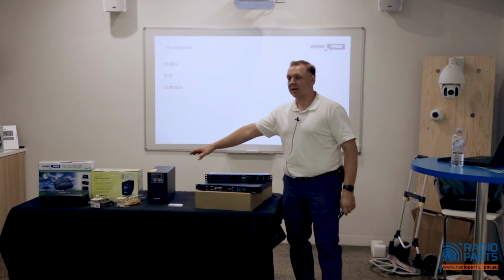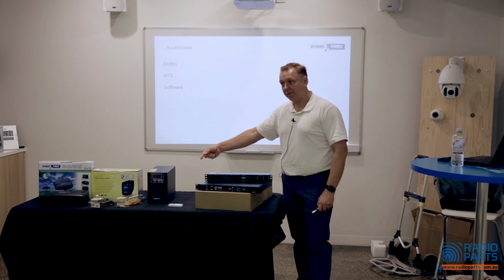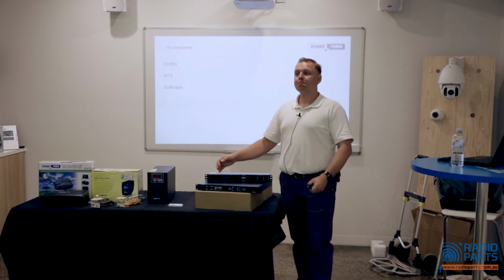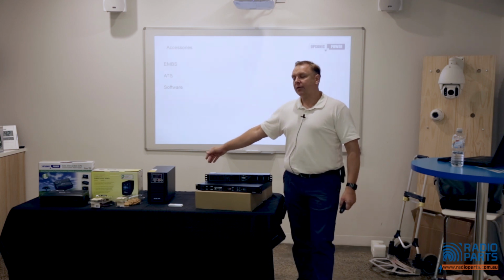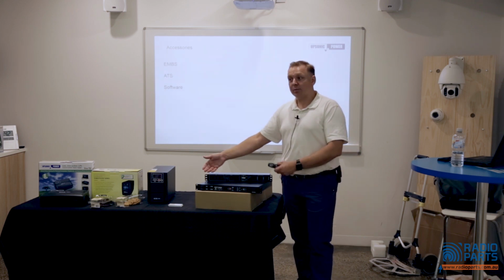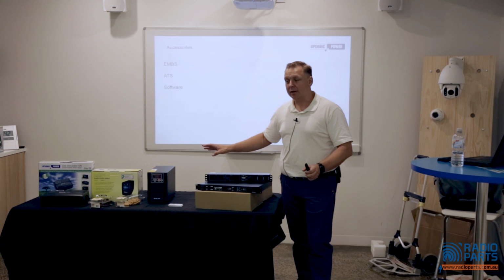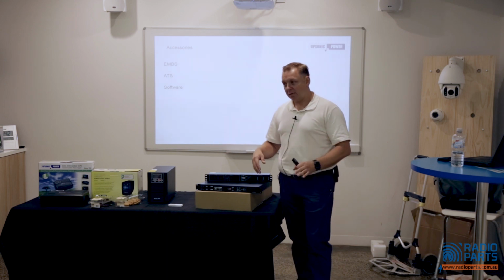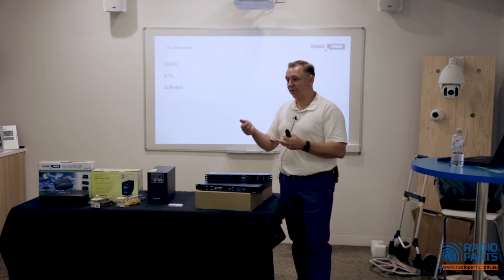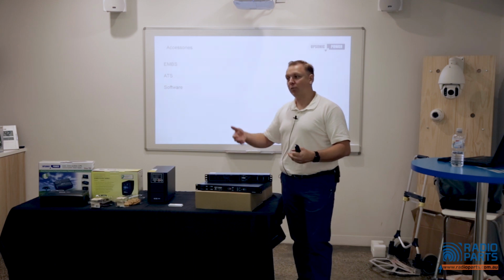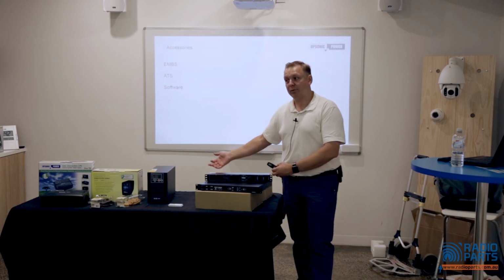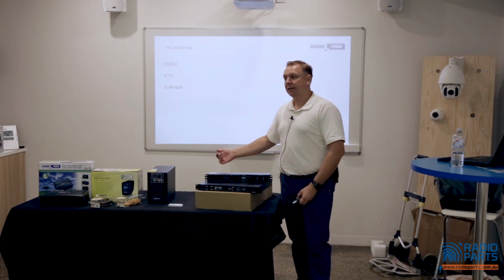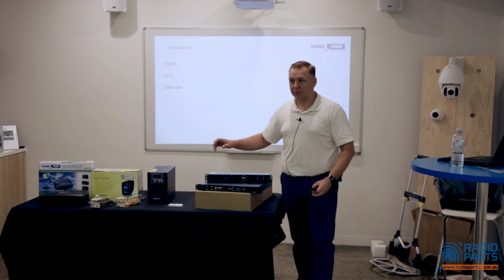You imagine you have a UPS like this and everything's plugged into the back of it. It just has sockets in the back. UPS fails, it might still be supplying the load, but the batteries are dead or whatever. Everything has to be shut down. You're then going to reconfigure and change how everything's plugged in, and then restart all of that equipment just before you can even start to do the maintenance. So this way, rotate the switch, done.